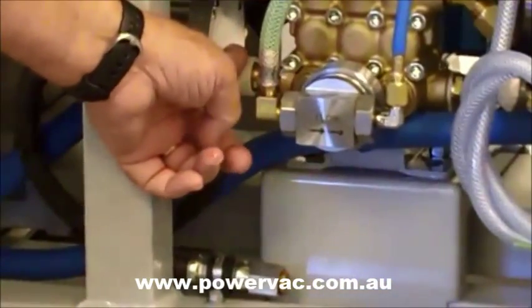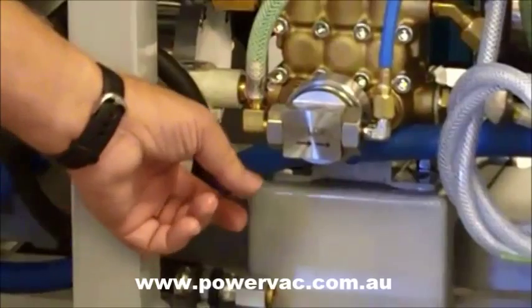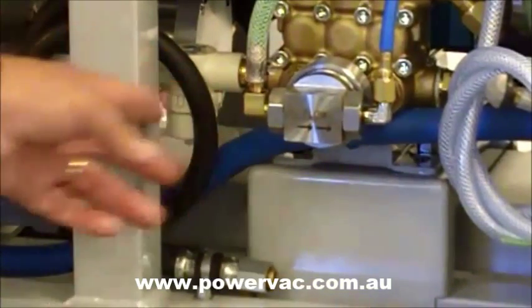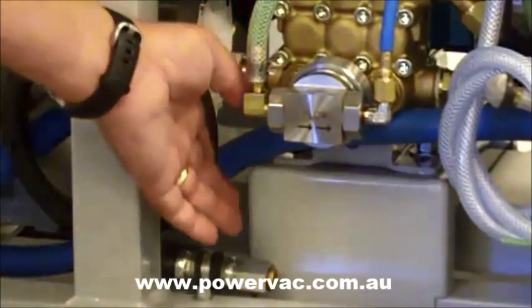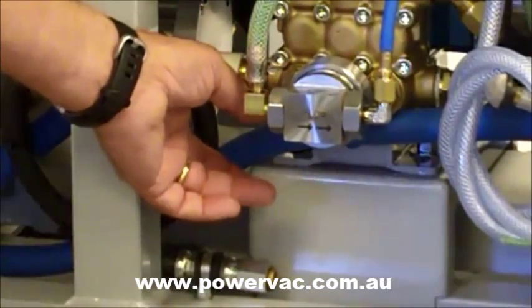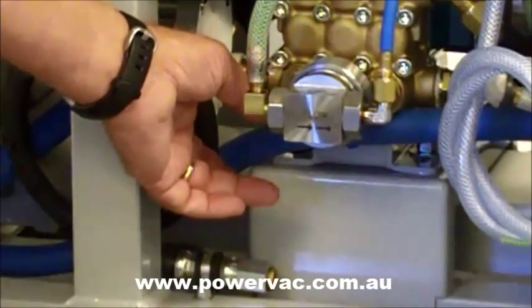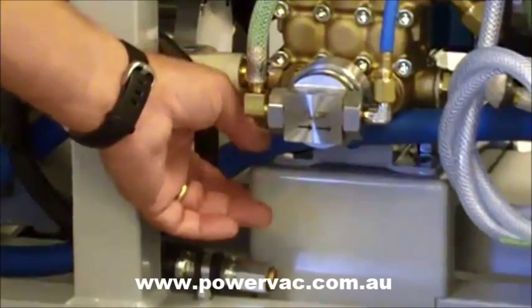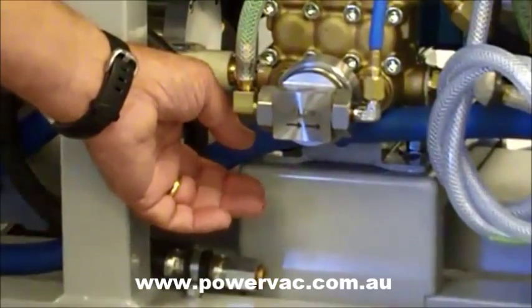Back in here on the inlet to the chemical pump is a filter, an inlet filter between the water box and the chemical pump. Another maintenance point. Depending on the area you're in, how dirty the water is, this may have to be cleaned out anywhere from once a day to once a year.